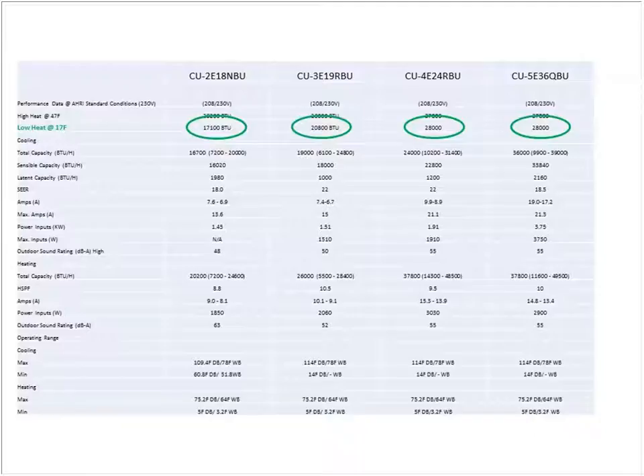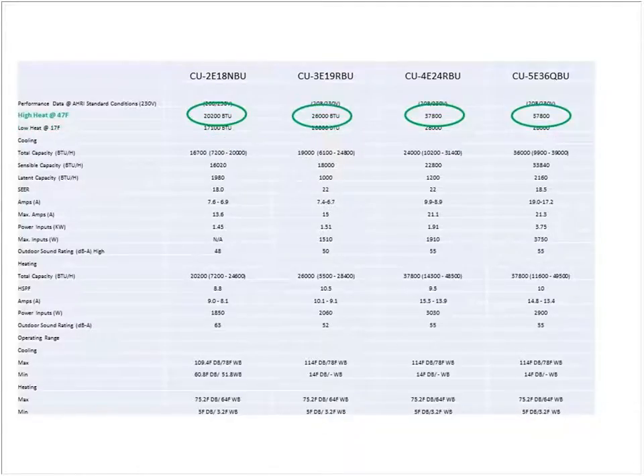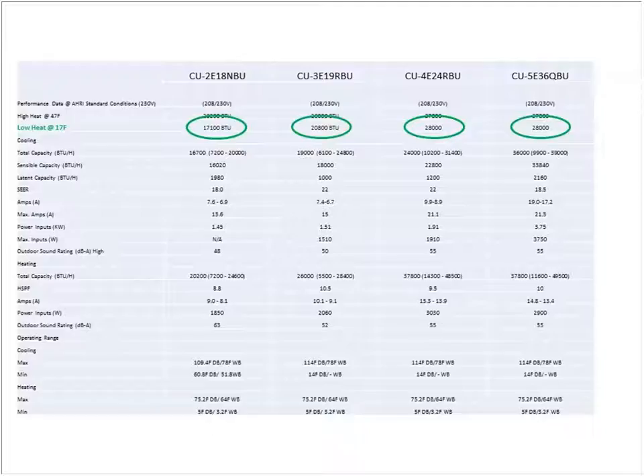So what I would want to have is some sort of redundancy heat control, whether it's a stick heater or who knows what. Here's a good example. We just put a bunch of these 4-zone systems in Kotzebue, Alaska. And we looked at the 4-zone versus the 5-zone, and I don't even get more BTUs on the high end. I get the same amount of BTUs. So we went with the 4-zone because it's considerably less money. But we were looking for that 28,000 BTU output at 17 degrees.